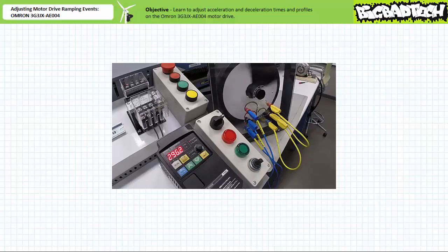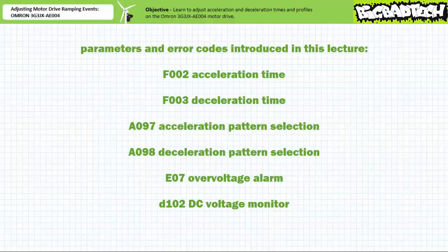Notably, the heavy flywheel decelerates to a speed I can stop with my finger in only 13 seconds, whereas previously I had enough established inertia to rotate for just shy of 6 minutes. 6 minutes of waiting just got reduced to 13 seconds. In conclusion, we learned to change acceleration and deceleration times and profiles on the Omron 3G3JX AE004 motor drive and observe their results. Additionally, we learned to recover the Omron 3G3JX AE004 motor drive from an over-voltage event during deceleration and increase deceleration time to accommodate loads with large rotational inertia.